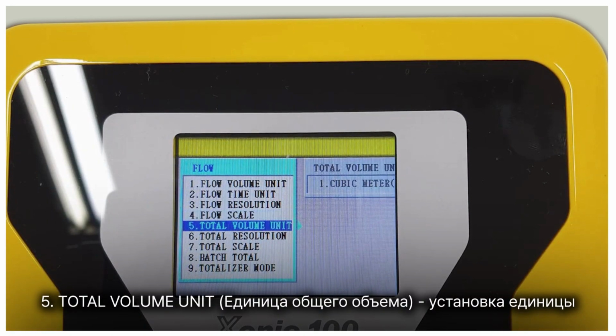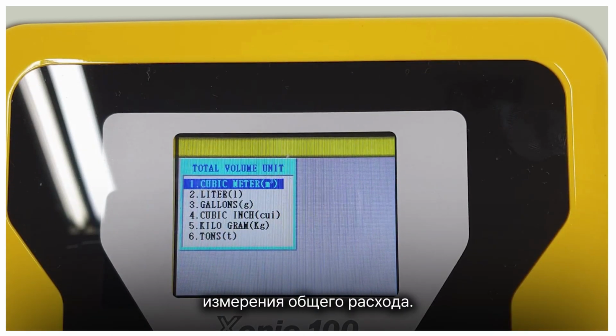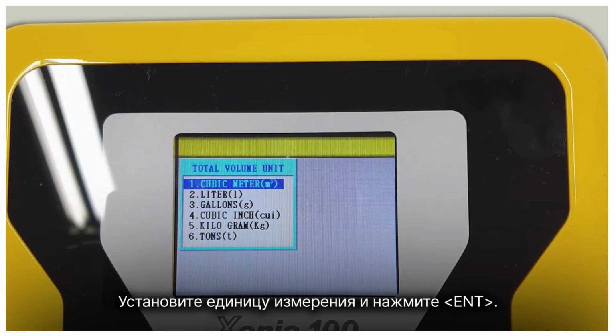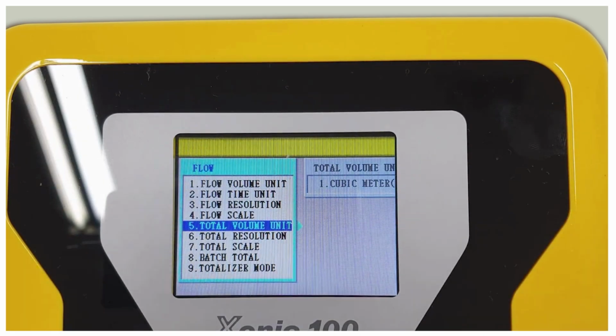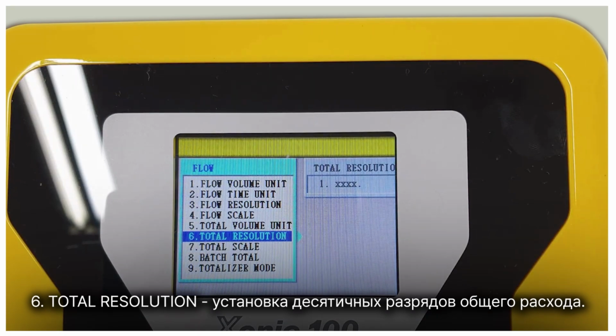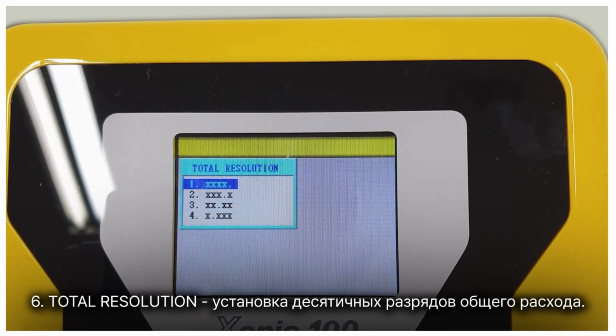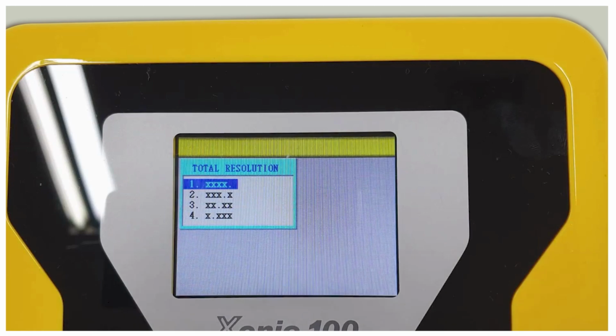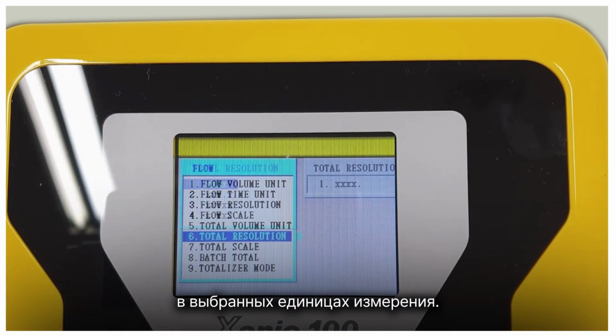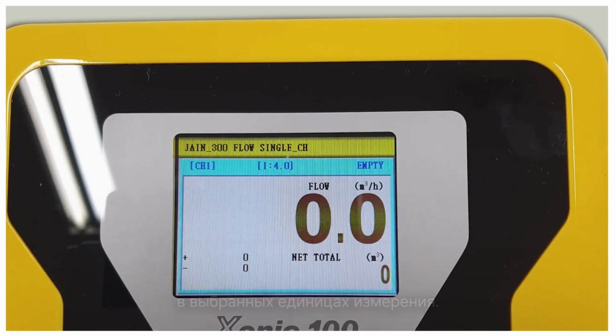5, Total Volume Unit is to set the unit of total flow. Set the unit and press Enter. 6, Total Resolution is to set the decimal places of the total flow. Press Menu and you will see the flow rate in the selected unit.